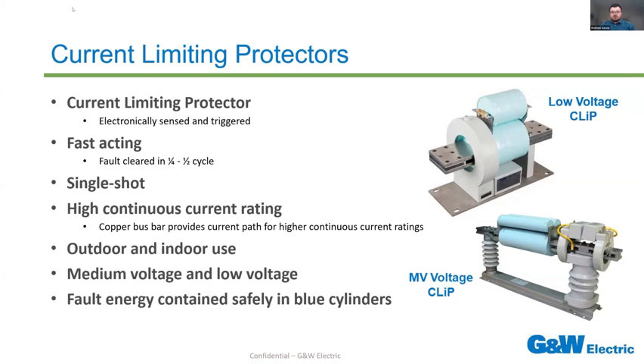There are medium voltage and low voltage options. Medium voltage goes up to 38 kV, low voltage up to 750 volts. And once again, just emphasizing that when a fault does occur, all that fault energy and all that pyrotechnic energy is going to be completely and safely contained within those blue cylinders. There's going to be no exposure to hazards such as shrapnel or ionized gases. All of it is completely safely contained. The only additional hazard that you would experience is the sound of a loud noise like a small caliber rifle going off. But working in the electrical area, you're probably already going to be equipped for dealing with noises like that. So it shouldn't be too much of an issue.